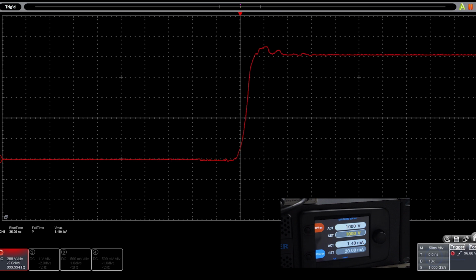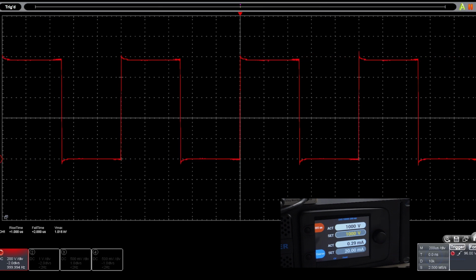Now, if there's an issue and we want to quickly turn the voltage down, we can disable high voltage and it will drop very quickly. Or we can either from the front panel or through a command decrease the voltage of the EVO to 0, and it will ramp back down at the same rate. Here the EVO is set to 0 and it just takes some time to ramp back down to that.